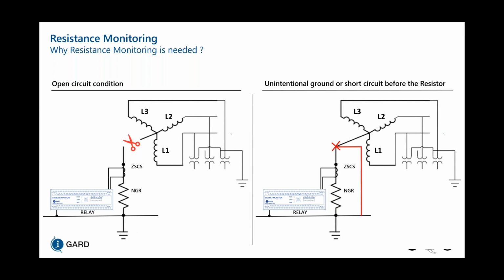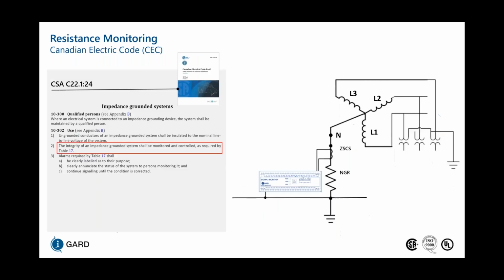In addition to that, when we experience a short circuit scenario, we see that the ground fault current may bypass this CT. So it may either split between this short circuit and the NGR path, or it'll go right through the short circuit and bypass this zero sequence current sensor. So it's not guaranteed that we're going to pick up the fault current in this case. And as a result, our system is now solidly grounded, and we're no longer limiting the probability of an arc flash incident by limiting this fault current to a specific value using that neutral grounding resistor.